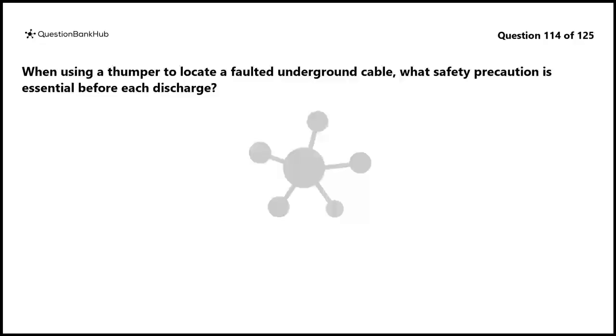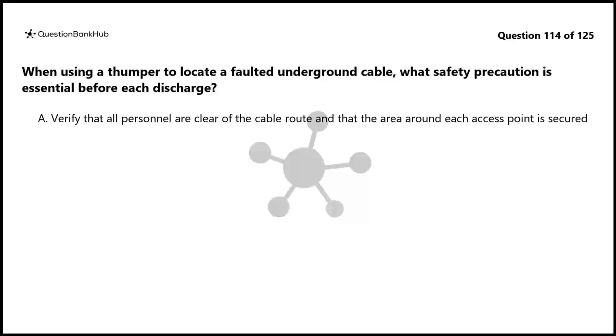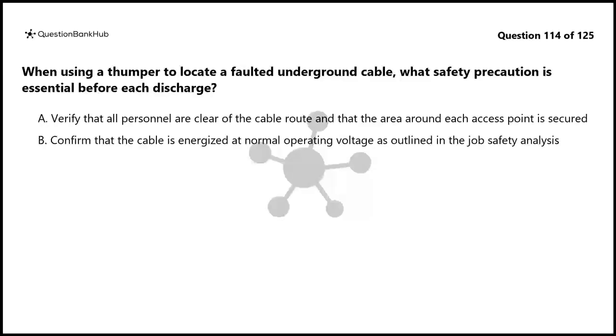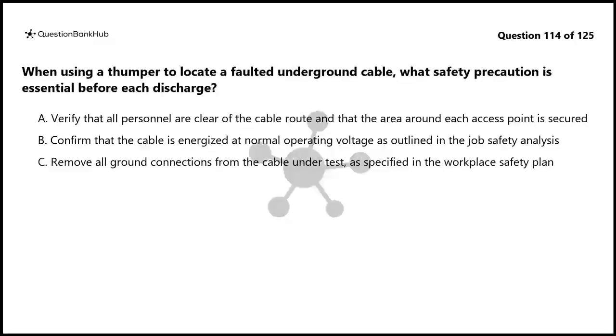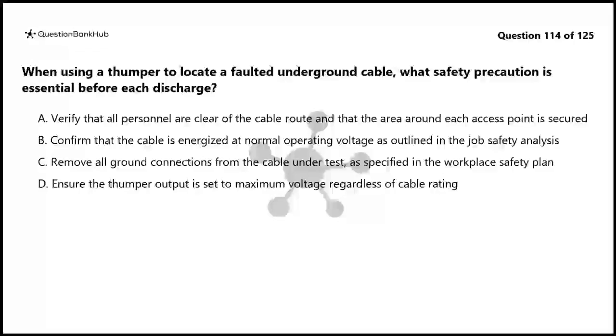Question 114. When using a thumper to locate a faulted underground cable, what safety precaution is essential before each discharge? A. Verify that all personnel are clear of the cable route and that the area around each access point is secured. B. Confirm that the cable is energized at normal operating voltage as outlined in the job safety analysis. C. Remove all ground connections from the cable under test, as specified in the workplace safety plan. D. Ensure the thumper output is set to maximum voltage regardless of cable rating.